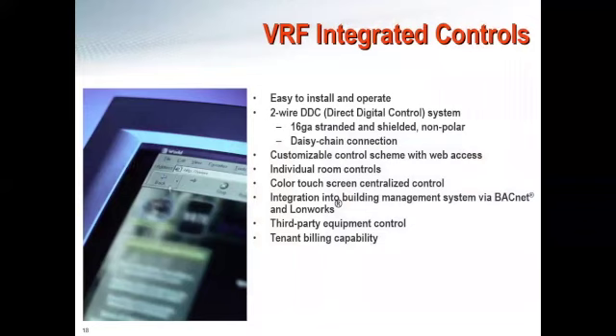So, integrated controls. I'm not going to get too deep into this and bore you with a lot of in-the-weeds details, but one thing I really want to highlight is that VRF systems are extremely flexible with the type of control that they can either accept or output. Like we said earlier, VRF can be controlled by something as simple as a standard on-the-wall thermostat, which can control most typical VRF systems, whether they're residential or a large commercial system. But once we start getting into the larger, more commercial systems, we see the need for building management systems and integration into things like BACnet, LonWorks, third-party equipment control, or tenant billing applications.